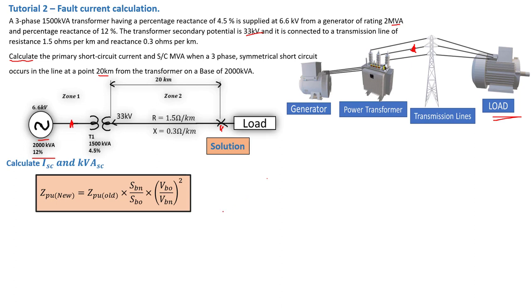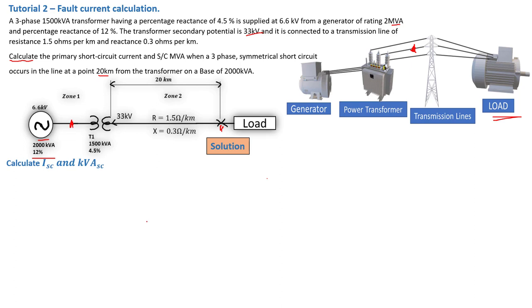Using the general per unit formula, we find the per unit of the generator (Z1) to be 0.12 per unit. For the transformer (Z2), we found a per unit value of j0.06 per unit. We can now move on to calculate the per unit for the cable.